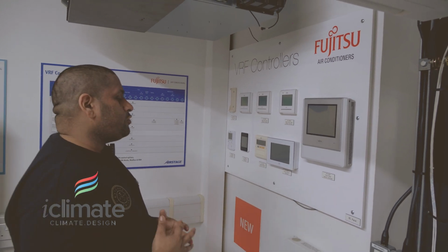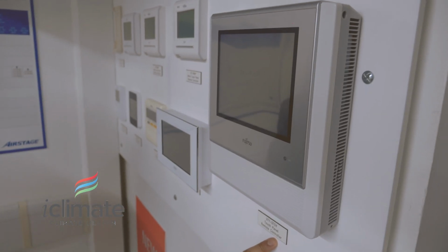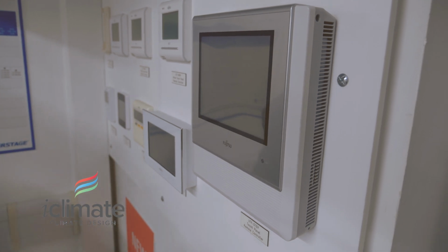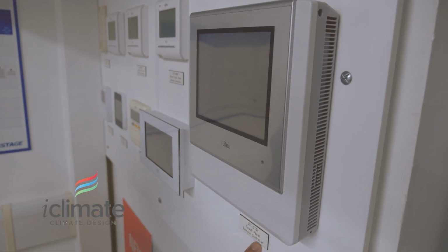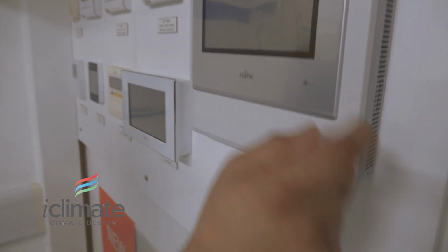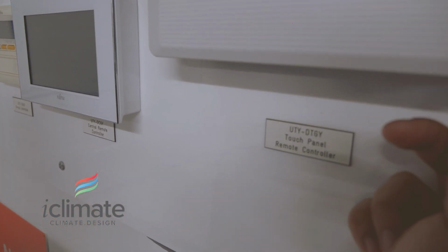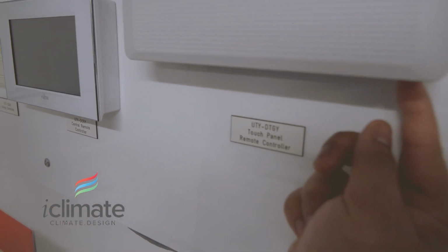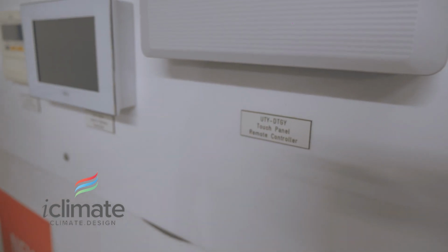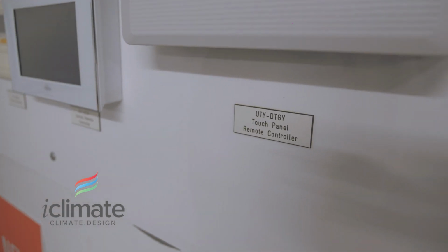Touchscreen options are central remote controllers that are essentially installed at a central point within the building. So the hotel would ideally want this within their maintenance office or back of house office, where the technicians and the staff can adjust the units, see the fault codes, and adjust rooms according to what the guests need.